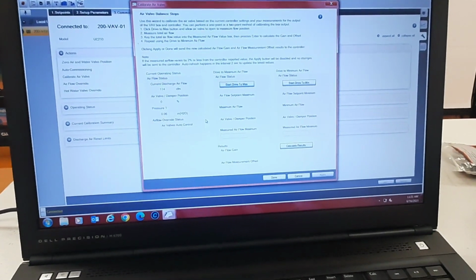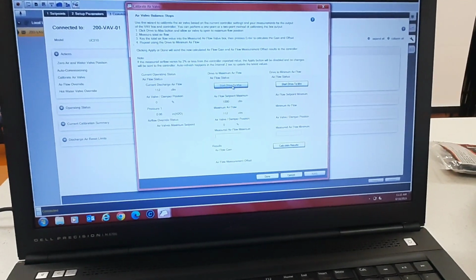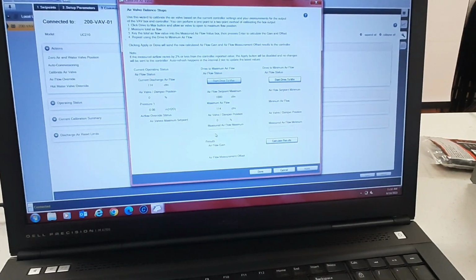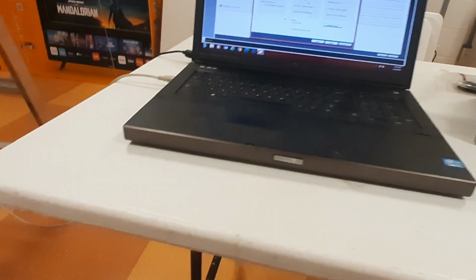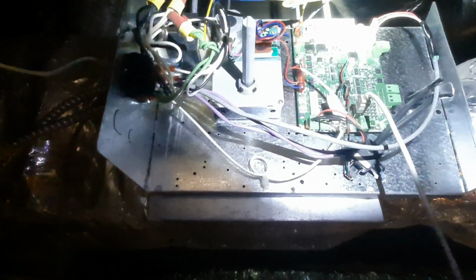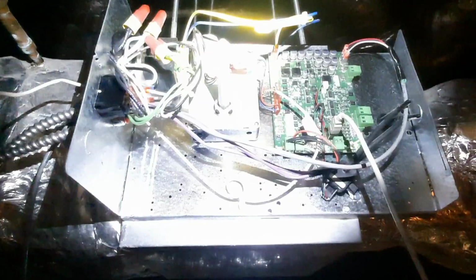This is the one that didn't work for me earlier, but we're gonna give it a shot again. Start drive to max. Doesn't give me apply, it just says measured airflow maximum, so it should be driving, I would assume. And it's not gonna drive from there. It opens counterclockwise and she ain't moving. You can see on my actuator I got no LED. Now that's an analog signal. I don't think it's a binary like the water valve is.